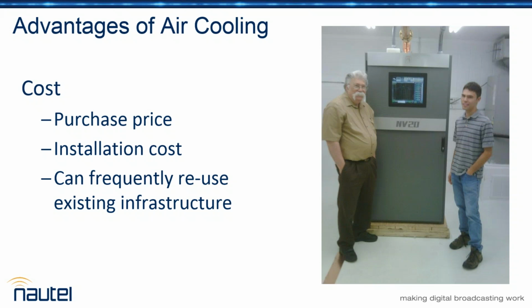Well, I think another thing that sometimes people are misled about is that there will be a comparison of efficiencies of transmitters, and they will compare a fully air-cooled transmitter, and that includes all of the energy consumed by the fans and blowers, with a transmitter that is liquid-cooled, but they don't include the pumps, and they don't include the fans that are on the external heat exchanger outside. And so it kind of makes the comparison a little less accurate.